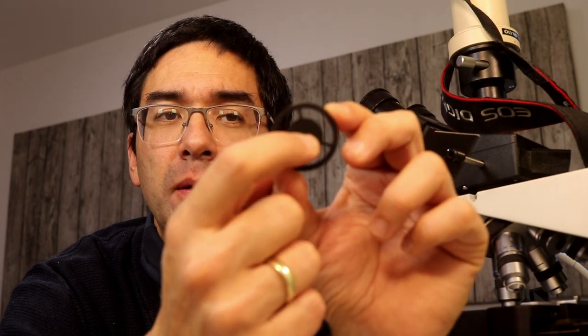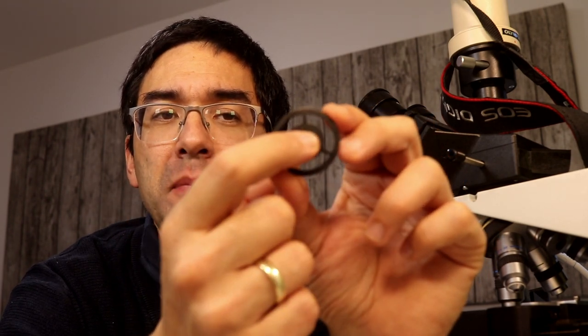The ring here on the outside is only there to center the patch stop in the filter holder, it has no real function otherwise. What happens is the central patch stop here blocks out the main microscope light so that the background becomes dark. And the light which strikes the specimen from the periphery, this light is then reflected back into the objective and that causes the specimen to light up on a dark background.